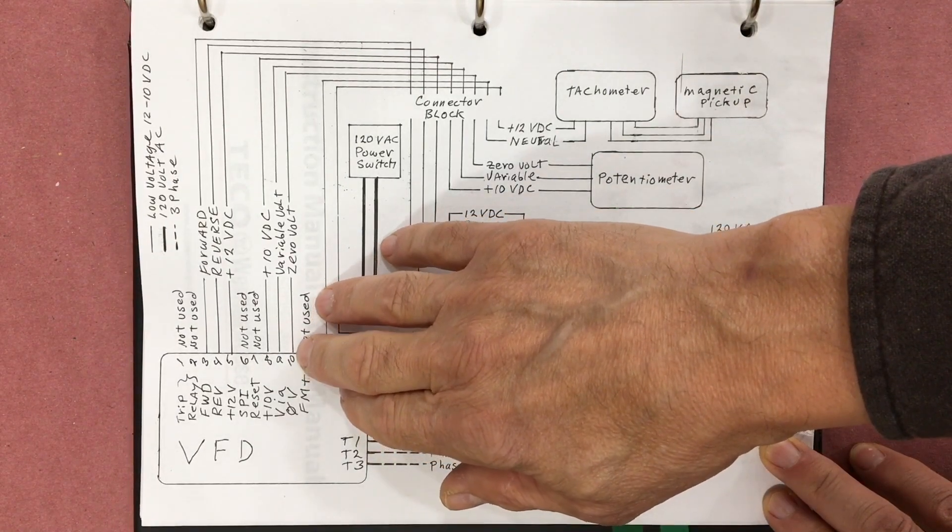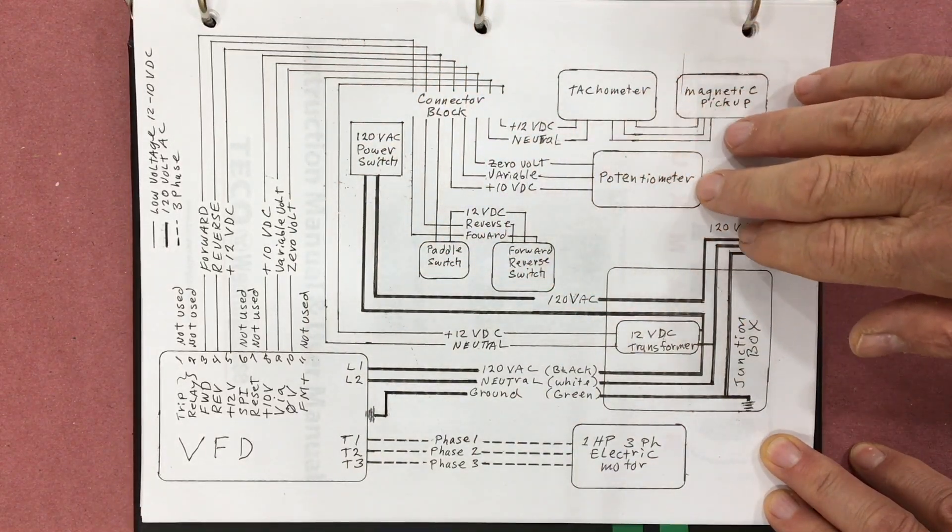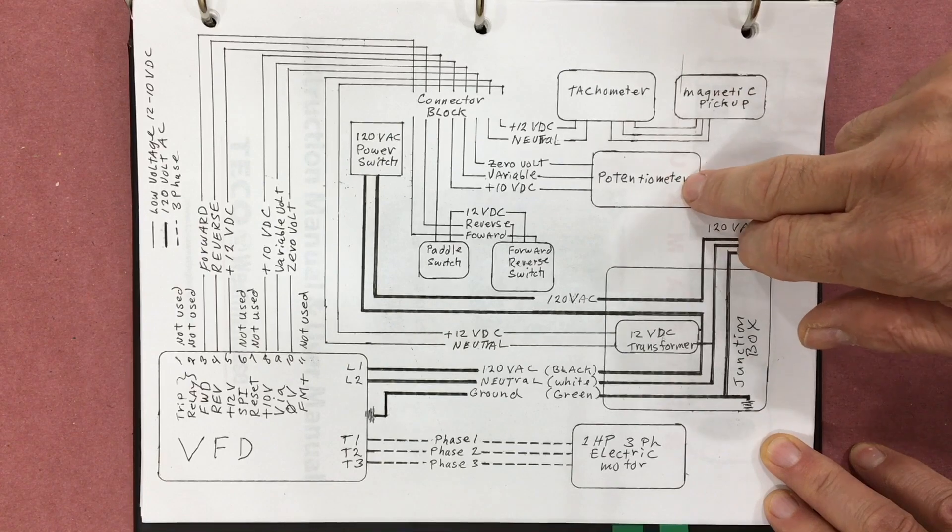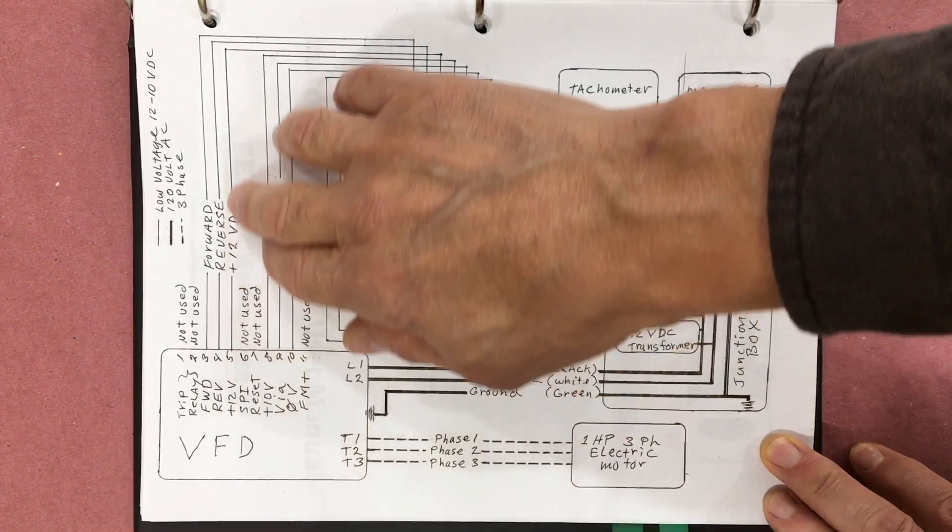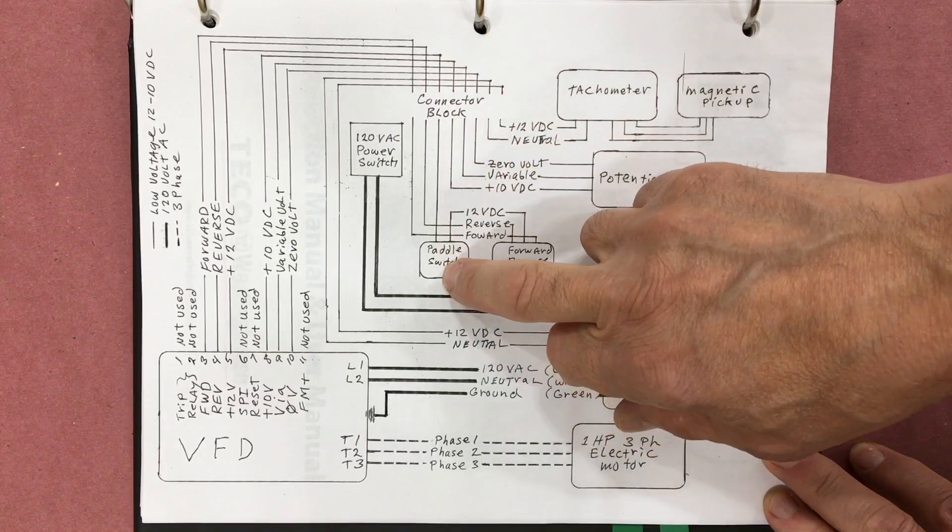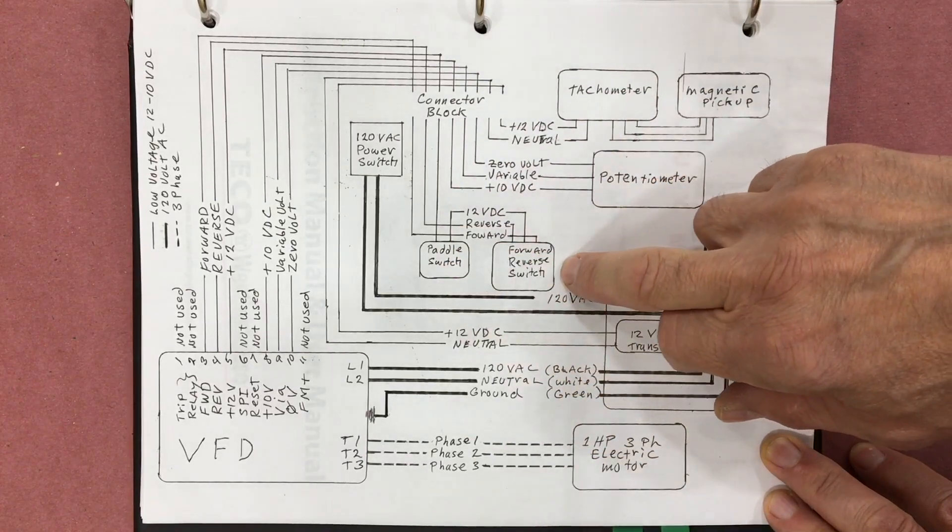There is a 10 volt circuit that comes from the VFD and it goes to the potentiometer that controls the frequency output for the VFD. And finally there is a 12 volt circuit that comes from the VFD, flows through the on-off paddle switch, and then to the forward-reverse switch.